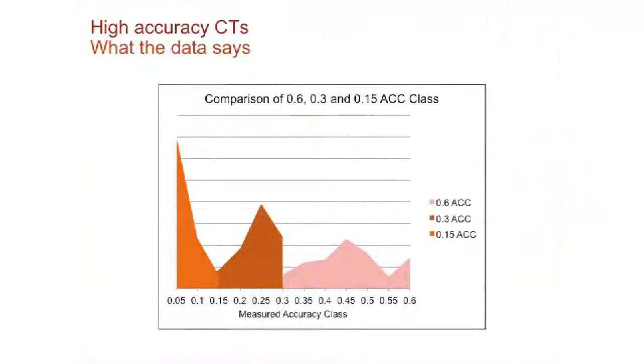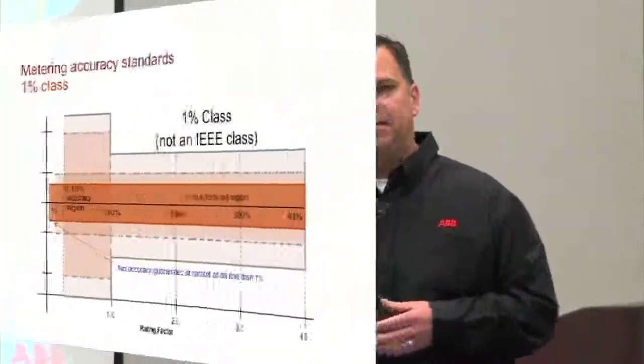So if we take a look at a chart of where a current transformer would need to be in the 0.6% class, you have to be anywhere between 0.6% above or below what we call nominal current. And this also runs the gamut from 100% of your nominal current all the way through what we call the rating factor. So you can have a rating factor up to 4 in a current transformer. So for instance, if you had a 200:5 rated CT, that could go up to 800 amps and would still have to measure accurately. Anything below nominal current, or in this case below 200 amps, the accuracy is allowed to fall off by double at that point.